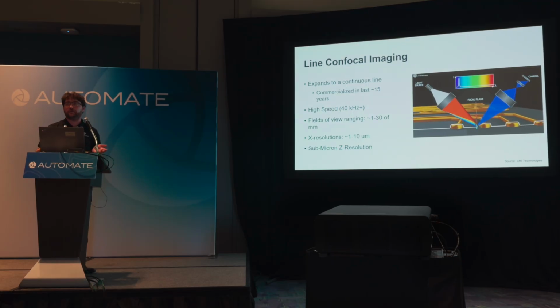your pixel. Right now, state of the art for that would be at around micron level X spacing. So you can get 2 and pretty soon 4,000 points at 1 micron spacing between each point. And then for each column, you basically are getting the spectral information, which gets converted into height.